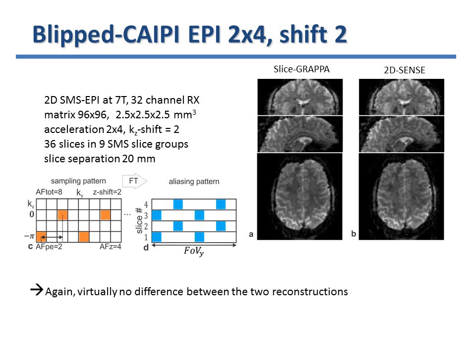Here we see the sampling pattern for a 2-fold in-plane and 4-fold multiband acceleration with a CAIPI shift of 2. The total acceleration factor is 8, resulting in 8 distinct peaks in the aliasing pattern. The CAIPI shift factor of 2 nicely distributes the aliased voxels over all slices and along the y-direction, which brings down the g-factor.